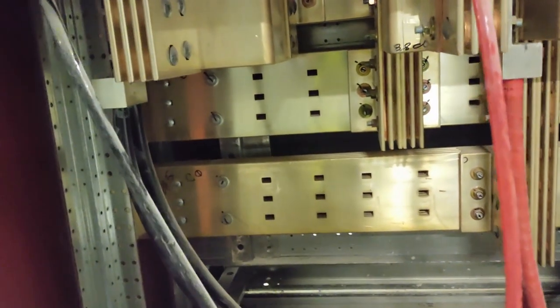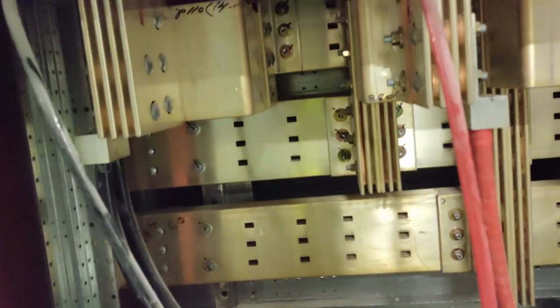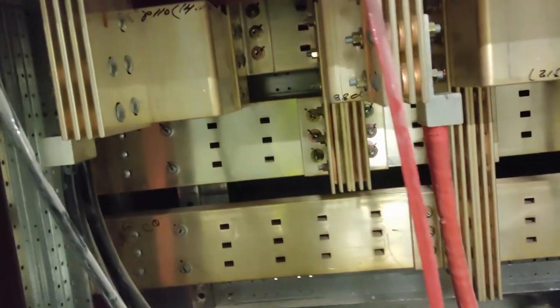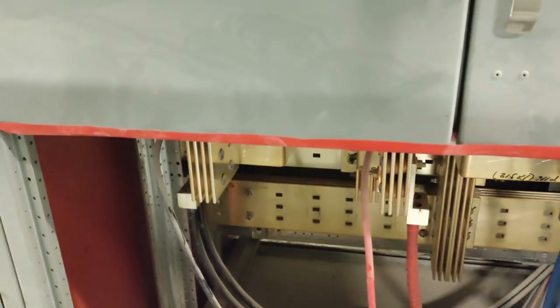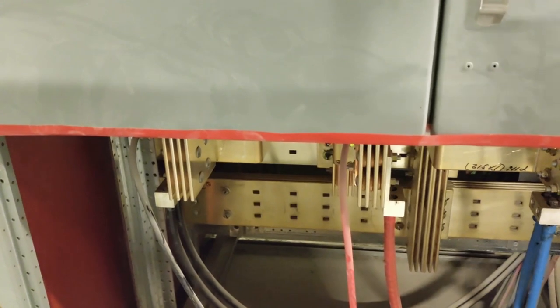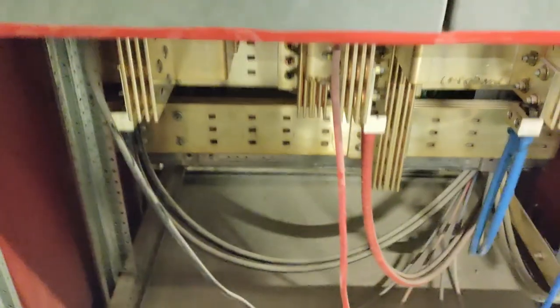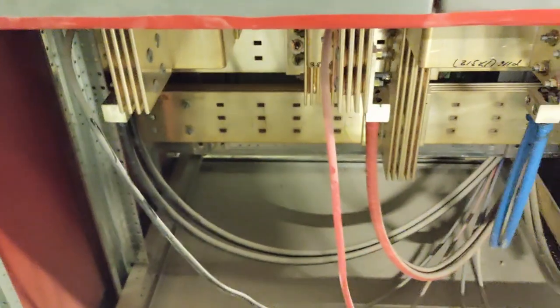I've seen a couple of people say that they actually go on the line side, but that's not correct. It has to go after the actual CT, on the load side of the CT. This way it can still get metered.